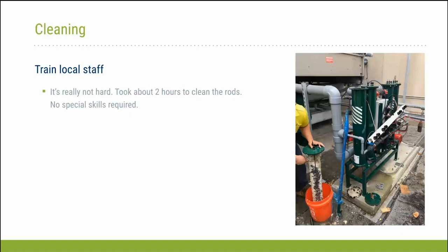Now, our incoming water here has a TDS of about 400 to 500 microsiemens, and when we were running the chemical system, we were running it about 2.5 times, okay, maybe around 1,200 or so. And during the demonstration period, the initial setting was 1,600, and a couple months later, they moved it up to about 2,400. And I think at the end of the demonstration, they actually went a little higher. They were close to 3,000, maybe 2,800 microsiemens, off of a 400 or 500 base. So we were running with about 5 cycles of concentration there.